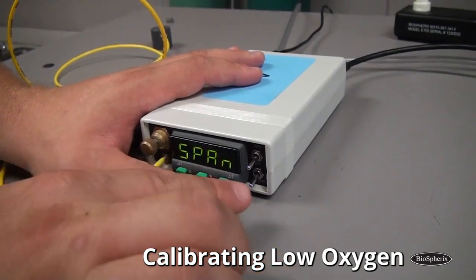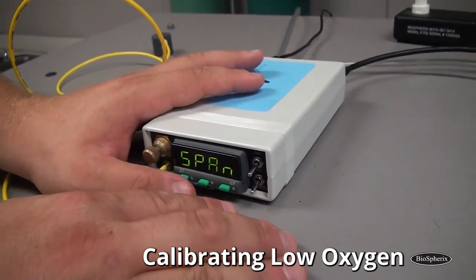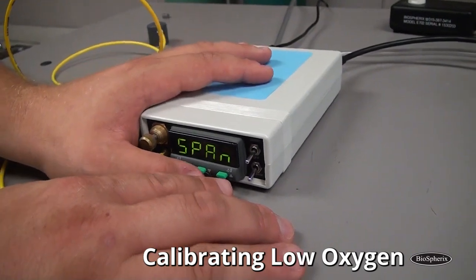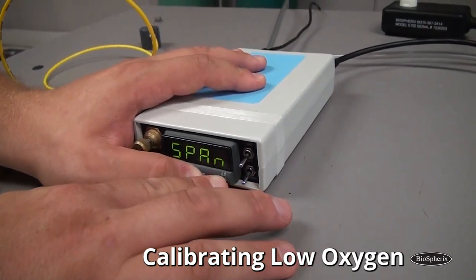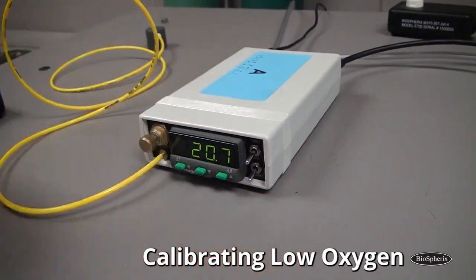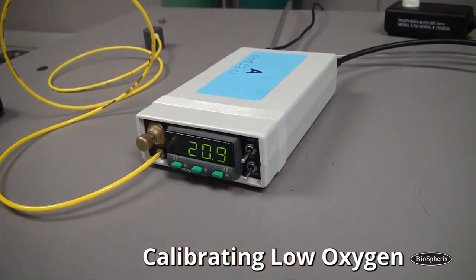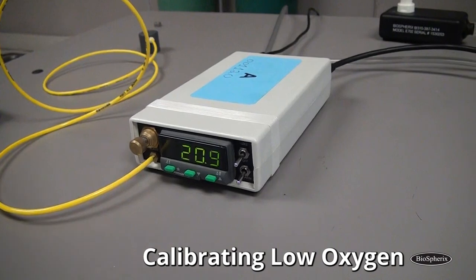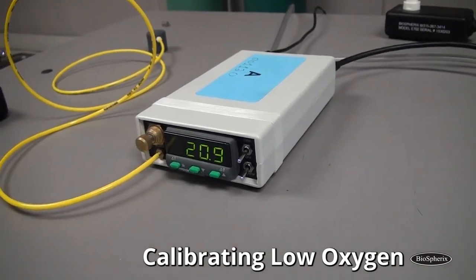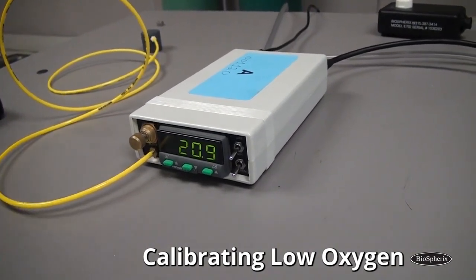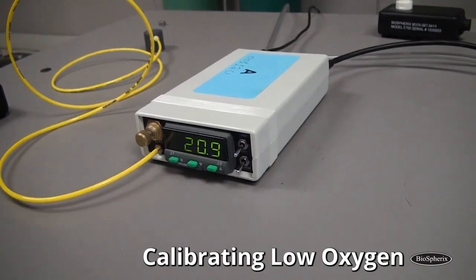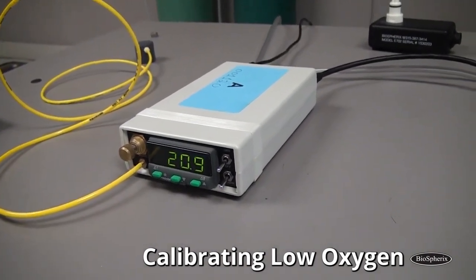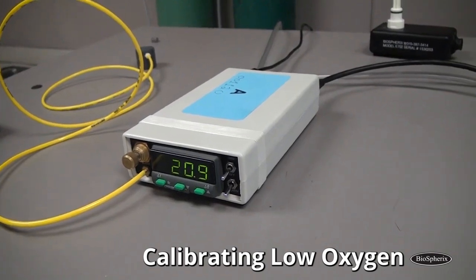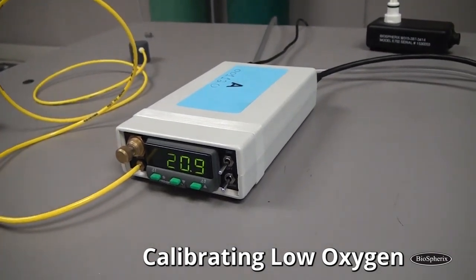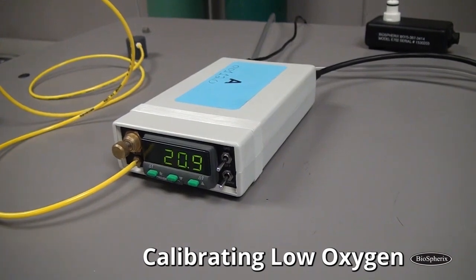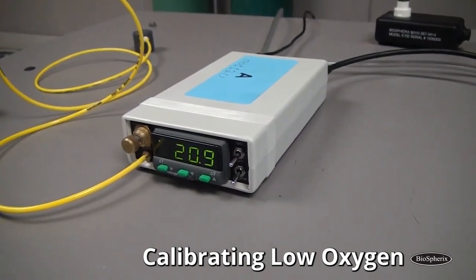So I've made a change to that function, and now I want to save that and exit the program mode, so I hold up and down for 3 seconds. And we see what it does. And we're at 20.9. The change worked. We're right where we want to be. You can play around with it if you want. If I try and raise that another one, or if I try and lower it one, it's going to be too far off. Again, it's a coarse adjustment, so you get as close as you can. So this is right on the money here, and we're good.